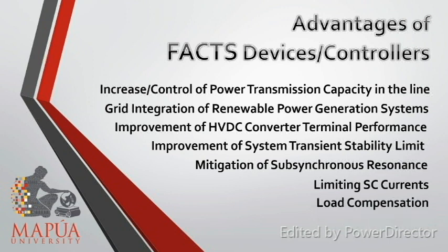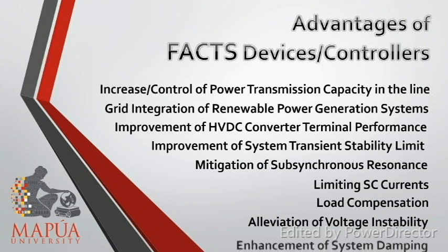FACTS also help in load compensation by management of reactive power to improve the quality of supply, especially the voltage and the power factor levels. For alleviation of voltage instability, FACTS provides direct voltage support to maintain sufficient line voltage for facilitating increased power flow under heavy loads and for preventing voltage instability. In the enhancement of system damping, FACTS increases the system security through damping electromechanical oscillations of power systems and machines.